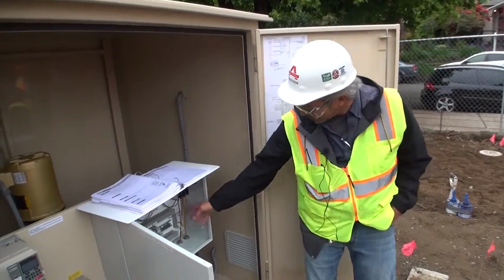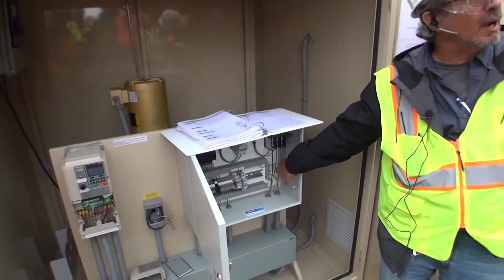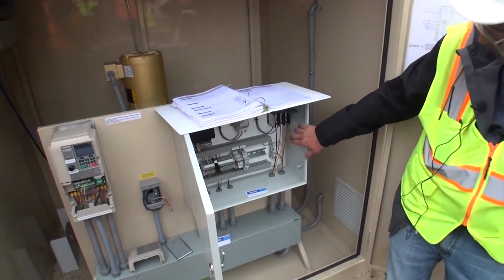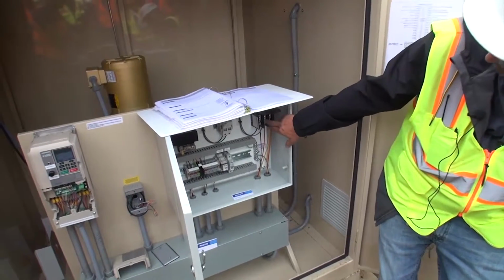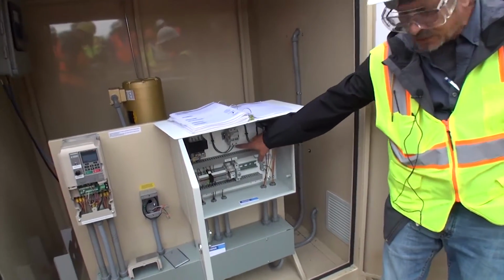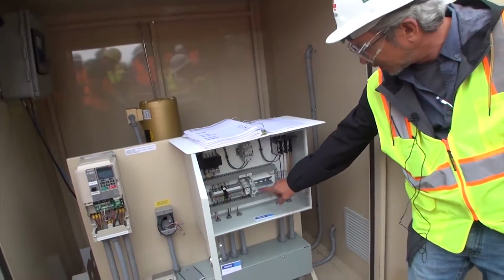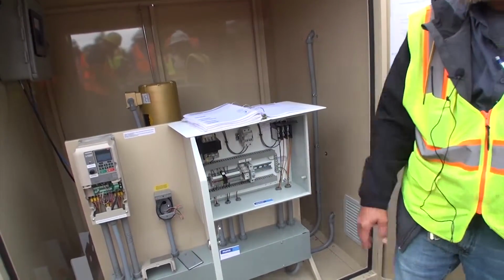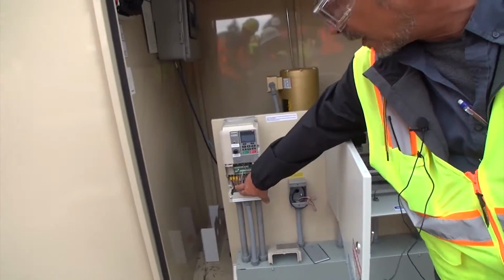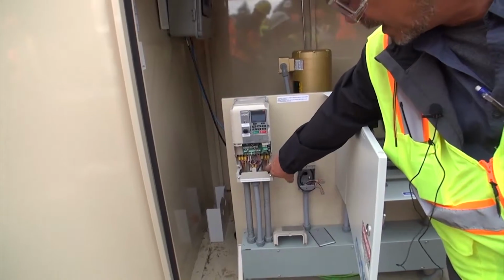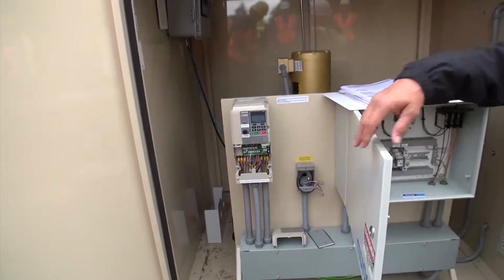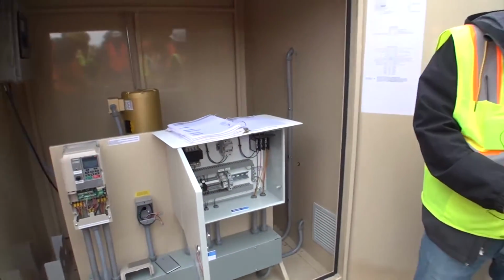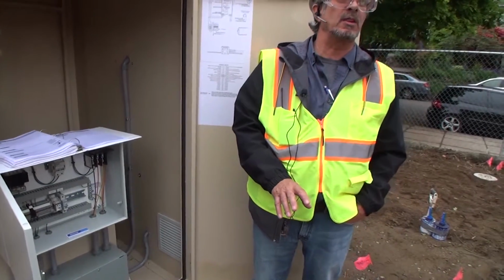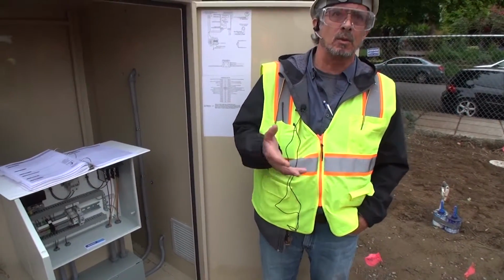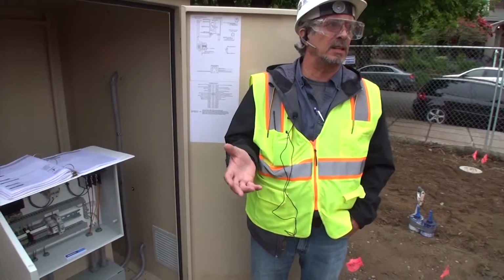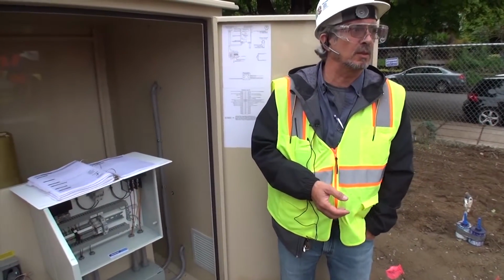You want to pay close attention to the connections, anything with the bigger wires. So you'll want to go through all of these screw connections and these Allen bolt connections. You want to do these fuse holder connections. You'll want to do these connections. You'll want to do these bigger wire connections here coming into the drive, and these three going out of the drives. The little wires, I'm not too worried about. They don't have a lot of current on them, so they don't get that hot, and they don't cool off much different. So not having the temperature fluctuations, they don't get loose. They don't work their way loose.